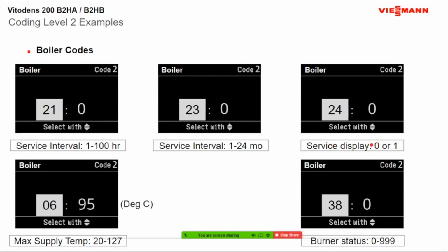What that means is you're allowing your boiler to tell you that it's time for the annual maintenance or annual service. It will put a wrench on the screen. So the question is, do I want a service display so Mrs. Jones can see that it's now time for my annual maintenance or not? Because we know that some homeowners, if they see a wrench on their screen and it's time for their maintenance, are going to get right on the phone and demand their annual maintenance immediately. So that's up to you.